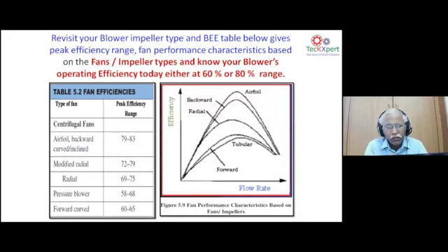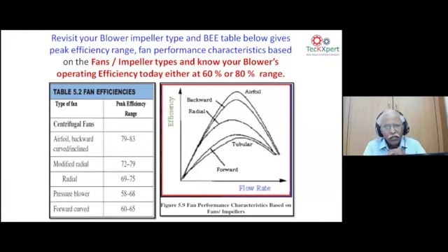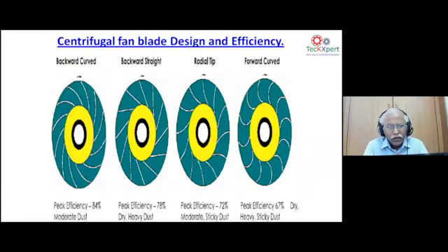Fans and impellers, per the BEE table, range from 60–80% efficiency. The key difference from motors — which have a flat efficiency curve of 50–90% across a wide range — is that blowers, especially backward-curved and airfoil types, have a very narrow efficiency band with respect to flow rate. We must match the static pressure of the system resistance to the system curve of the given blower to operate at the best efficiency point.